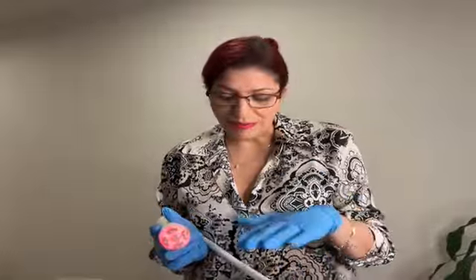of the skin. Now, we're not trying to achieve heating of the surface of the skin, but the surface of the skin we know is going to be 3 degrees colder than our deeper layers. So we know when we're achieving between 39 and 41 on the surface, in actual fact, we're 3 degrees higher, at 42 and 44 degrees. So hopefully my maths is right.